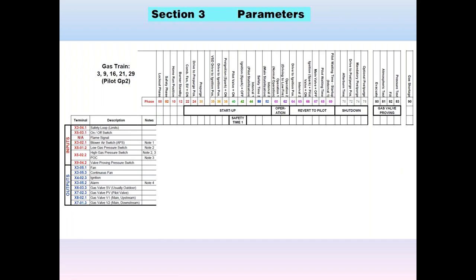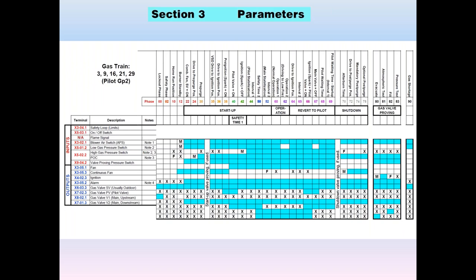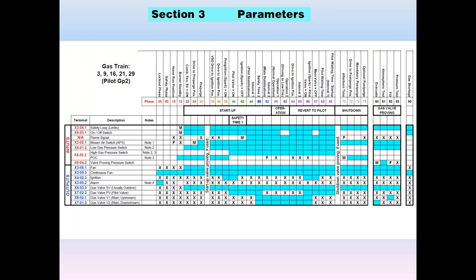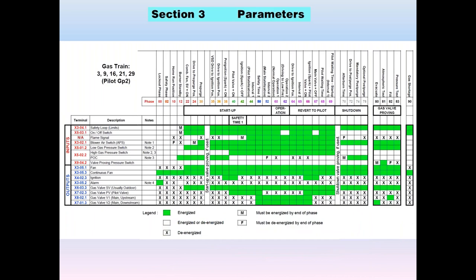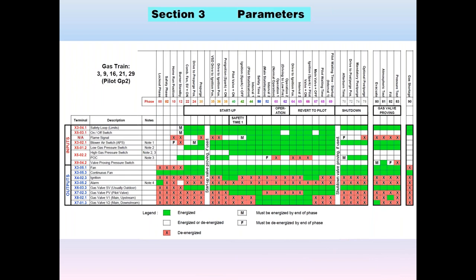In addition to the phases, we list all terminals on the LMV3. In red you see all input terminals, and in blue you see all output terminals. A chart shows when each terminal during each phase must be made or not made, with a legend at the bottom explaining it. You can see when terminals must be energized as inputs or are energized as outputs. Anything in white means the terminal can be in either state during those phases, and M's and F's indicate whether it had to be made at the beginning or end of the phases.